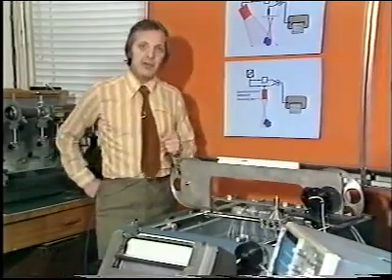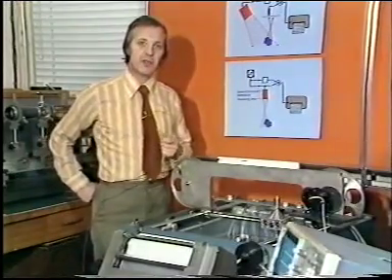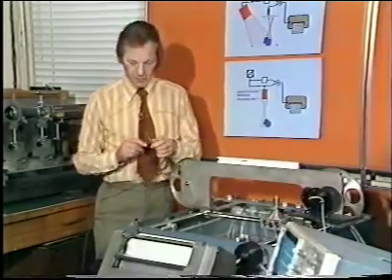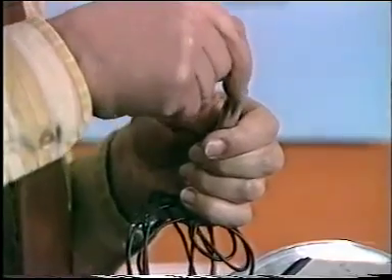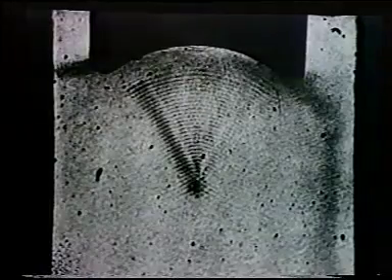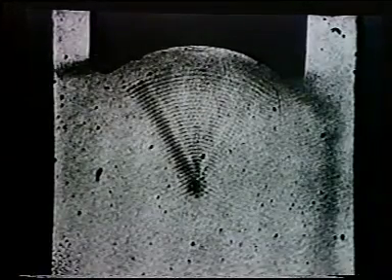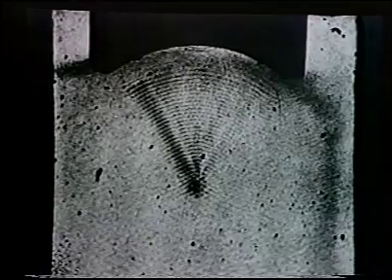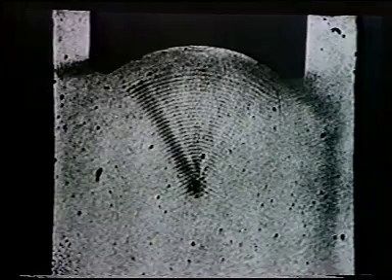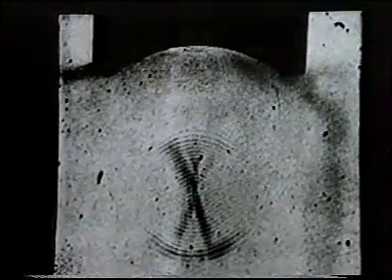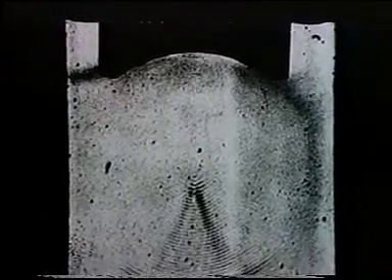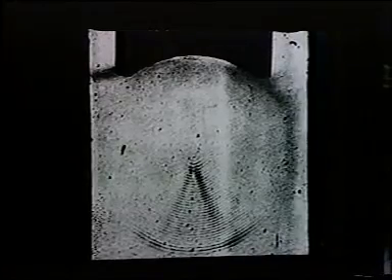Now, you may not be convinced that we can make such a transducer which will in fact focus in that manner. This is the actual transducer we use, and the surface is dished or concave, as I was just describing. But to convince you that this thing actually works, let's look at some Schlieren pictures. This first one shows you a shadow at the top of the concave surface which forms the transducer focusing lens. And you can see waves emerging and converging towards a focal point. They then pass through this focal point and emerge the other side as diverging spherical waves. Well, I hope that convinces you.